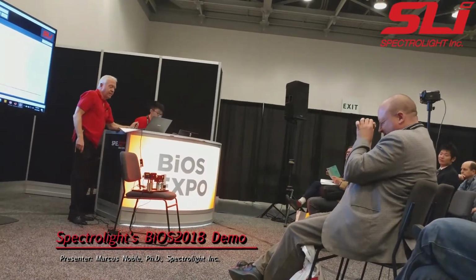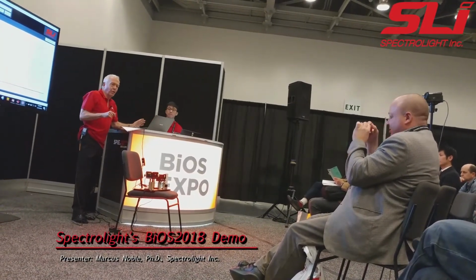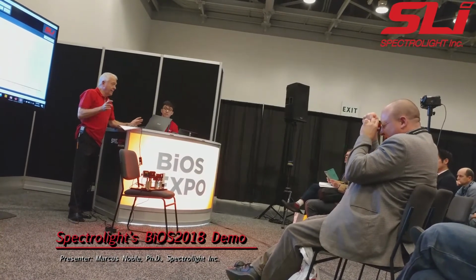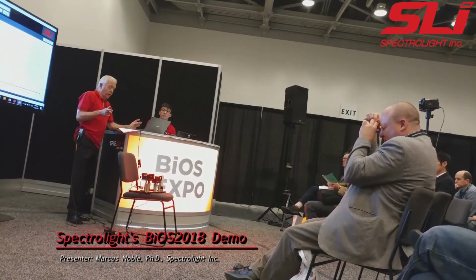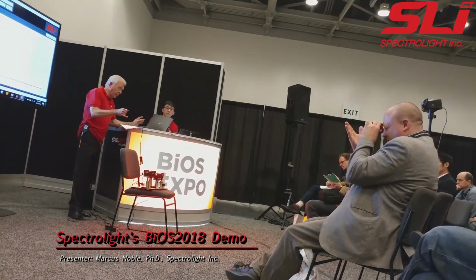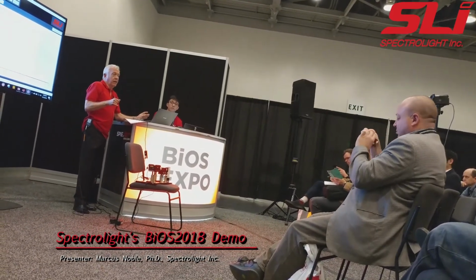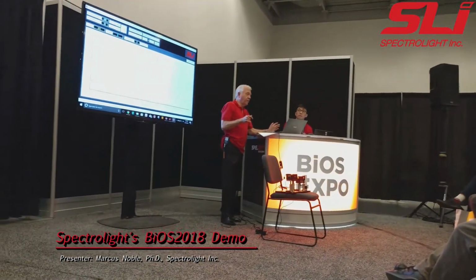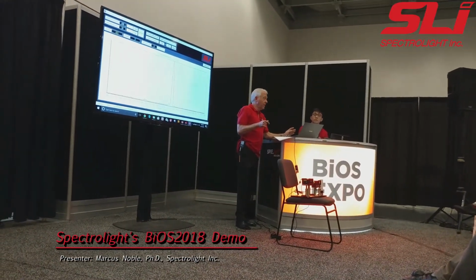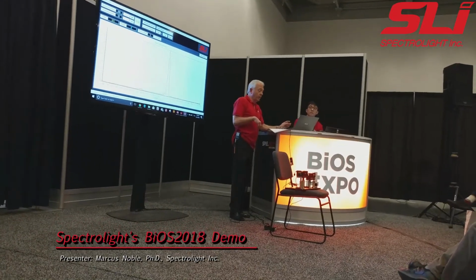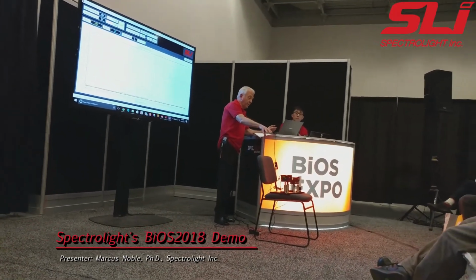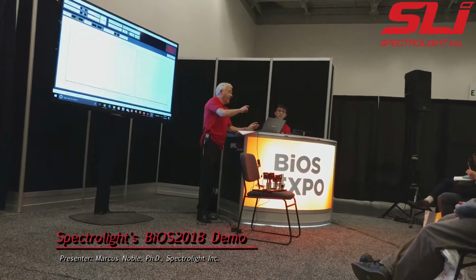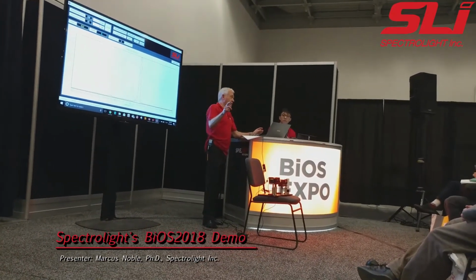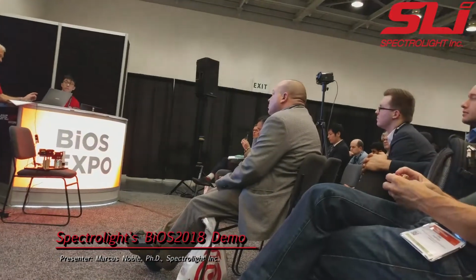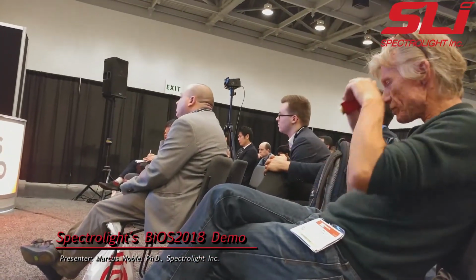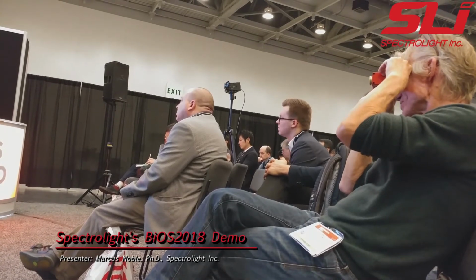If you're interested, I'm sure some of you, hopefully potential OEMs, if you come by the booth at 8739, you'll see we have a first instrument actually using this. It's a fluorimeter, and this particular fluorimeter is configured to look at new dyes, so it accepts cuvettes. And because of the agility of the flexible wavelength selector, we can scan the excitation spectrum as a function of emission, or scan the emission spectrum as a function of excitation, which is exactly the information biologists need today when they're looking at new fluoroprobes.